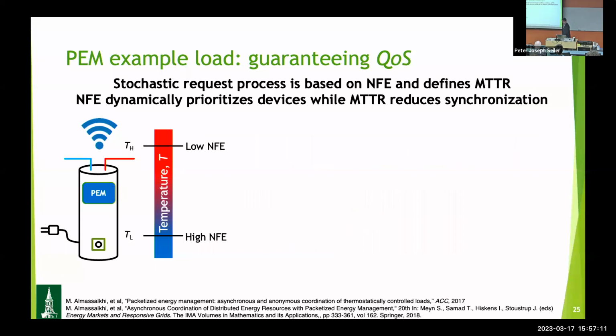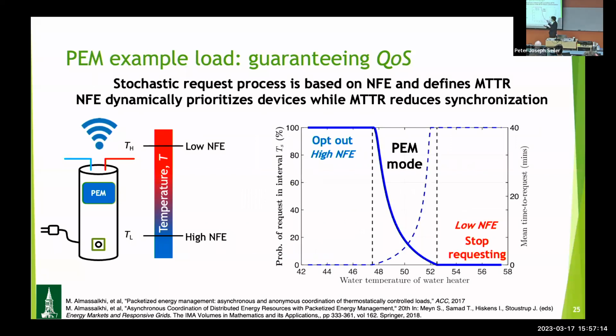The key part of packetized energy management: between the temperature limits of the water heater, in Celsius, you have essentially a mean time to request that is proportional to the temperature itself. The colder a device gets, the more likely it is to make a request. This allows you to dynamically prioritize which devices request first or more frequently than others, so when the grid has some capacity to hand out, it goes to the devices that, on average, have higher priority. It's effectively a dynamic prioritization scheme.